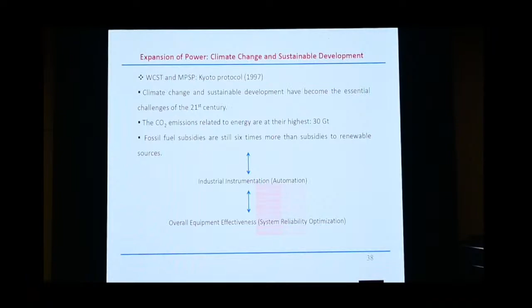That is an area in a thermal power plant where we have actually contributed. The application was to develop a new control and instrumentation system - a complete automation platform including the HMI for a thermal power plant where the prime mover size ranges from 200 megawatt to 660 megawatt. In India these are the standard sizes: 200, 220, then 300, 330, 400, 440, 500, 600, and 660 - it's not a variable size. So we developed two designs: one with higher redundancy, above 500 megawatt, and one with low redundancy, around 200.